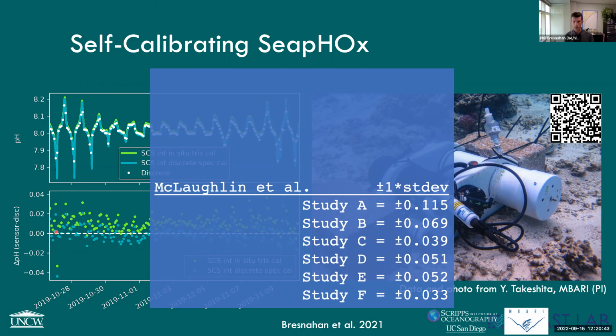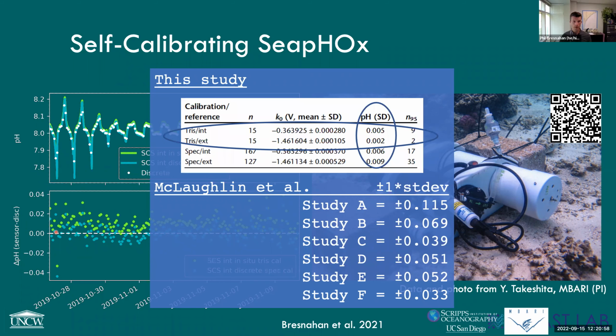And I'm throwing back up the McLaughlin et al. numbers here so that you can see this is, again, the semi-independent analysis of how these different sensors perform when other folks deploy them using best practices, our best ability to collect these discrete samples. And then overlaying on top of that, I'm showing what we were able to achieve with our tris-based calibration. With the internal reference electrode, we were able to get down to a standard deviation of 0.005 with 15 standards. And the external reference electrode, and I'm not going to get into the distinction between those two electrodes, but both of these are built into the standard SeapHOx, we were able to get all the way down to 0.002, and again with 15 samples. So really starting to approach those climate scale uncertainties that I mentioned. In the far right-hand column here, you see this other parameter. This is basically back calculating our 95% confidence interval.